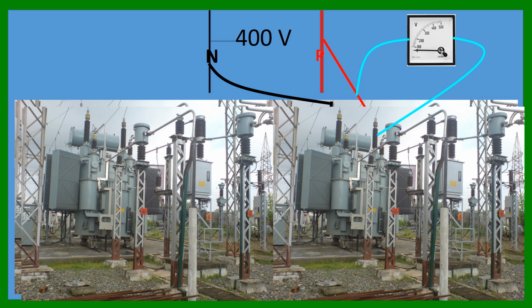Friends, this is the system of power transformer phase identification. It is called the AC test. Here we will give 400 volt AC and the output of the 25 kV side will be 75.76 volt, and connect just like my figure.